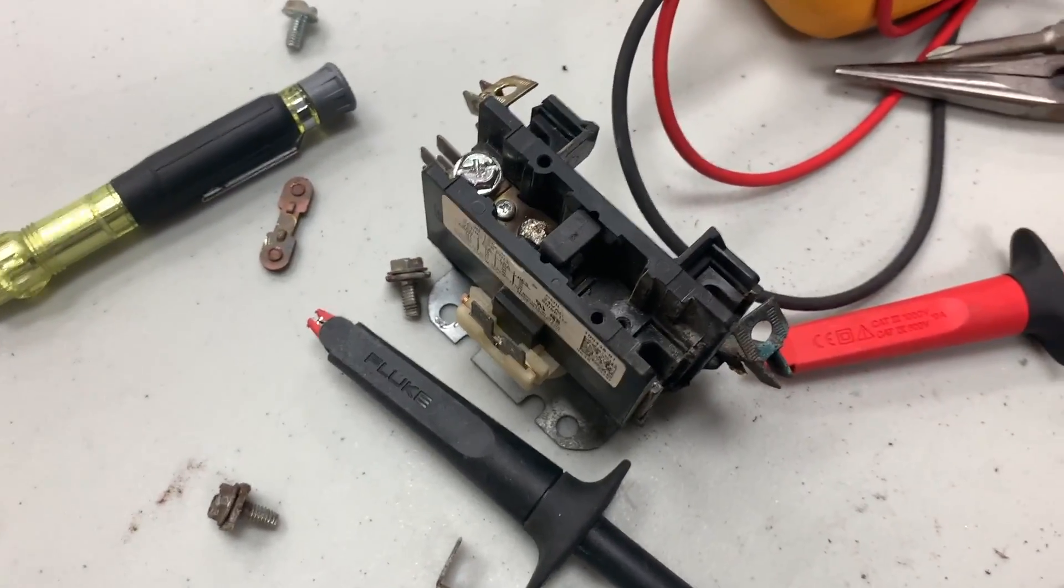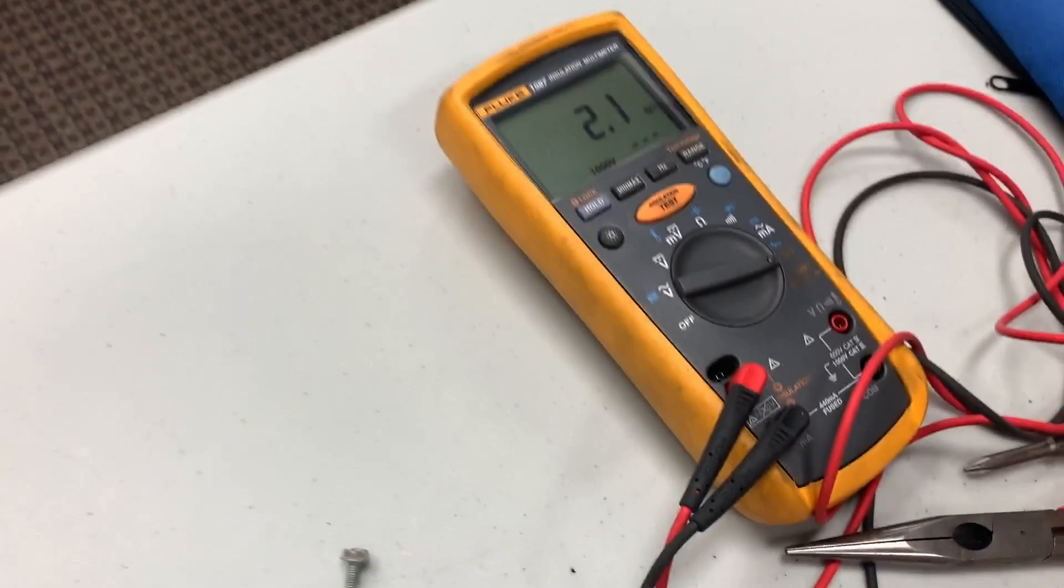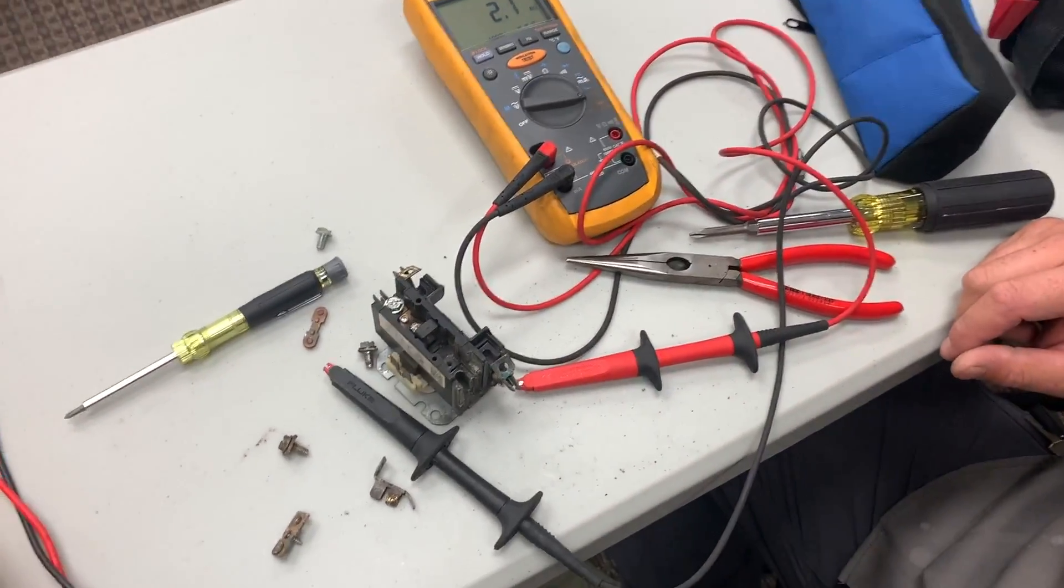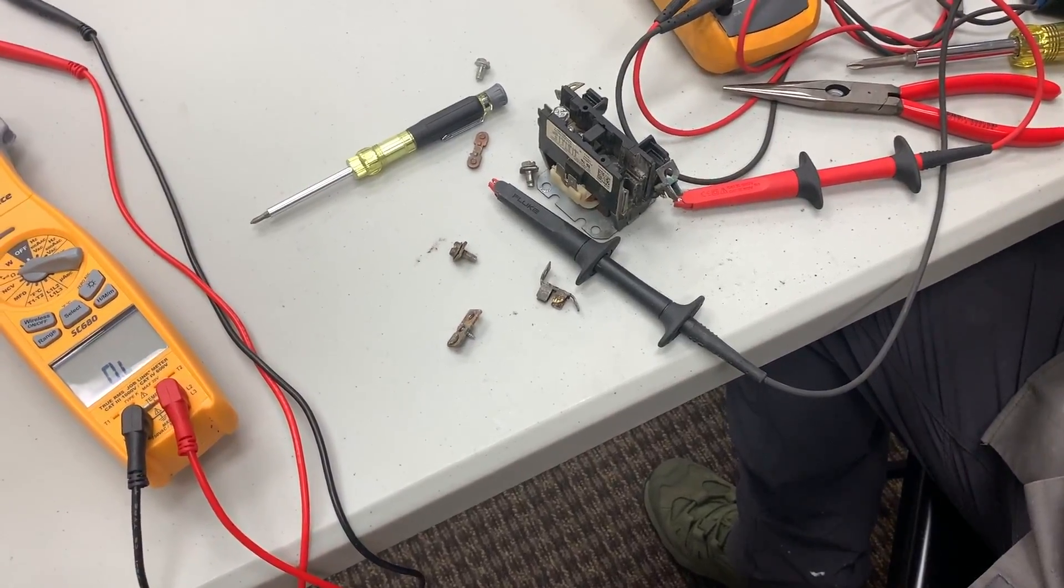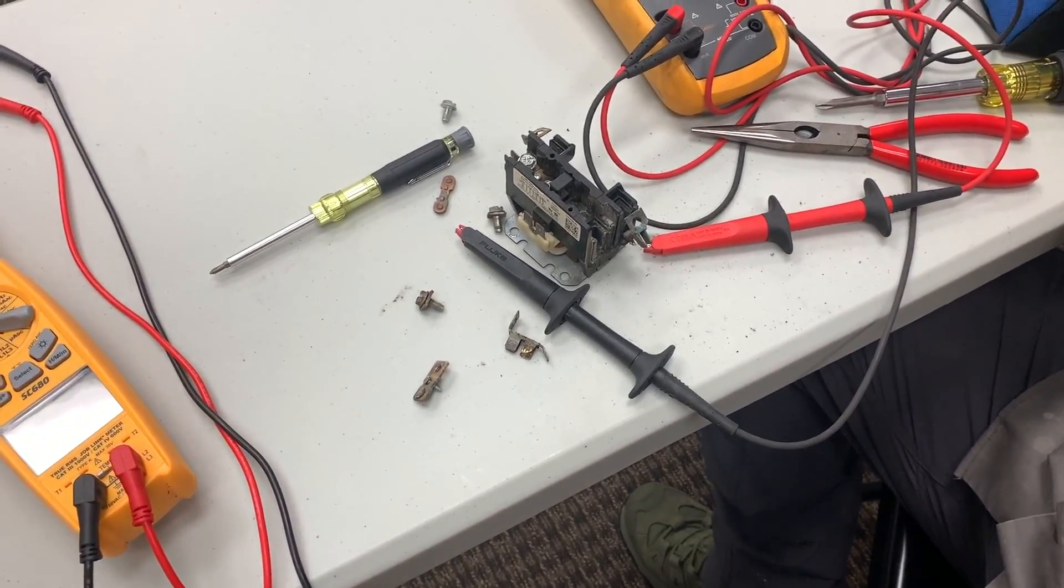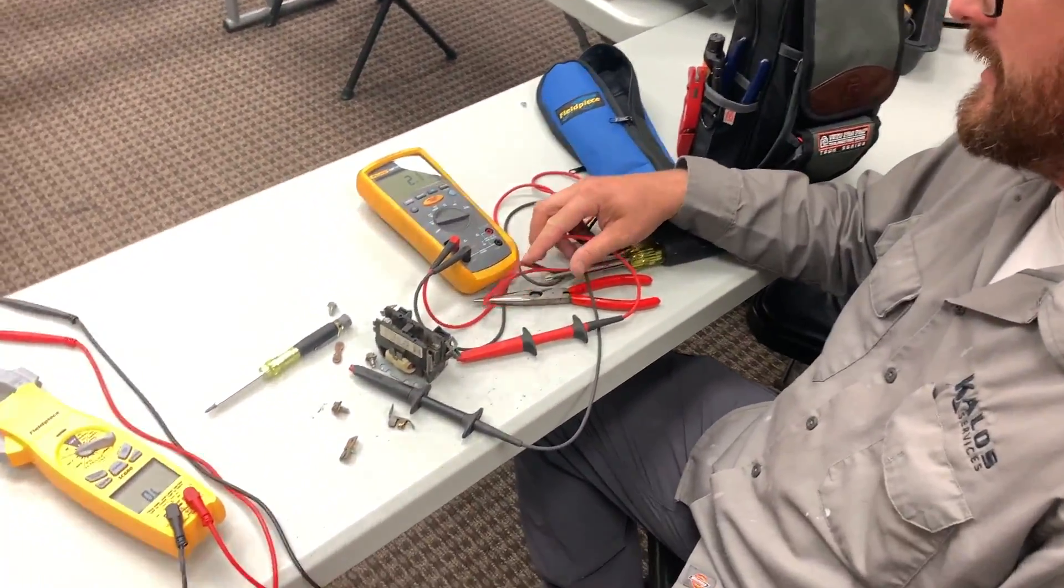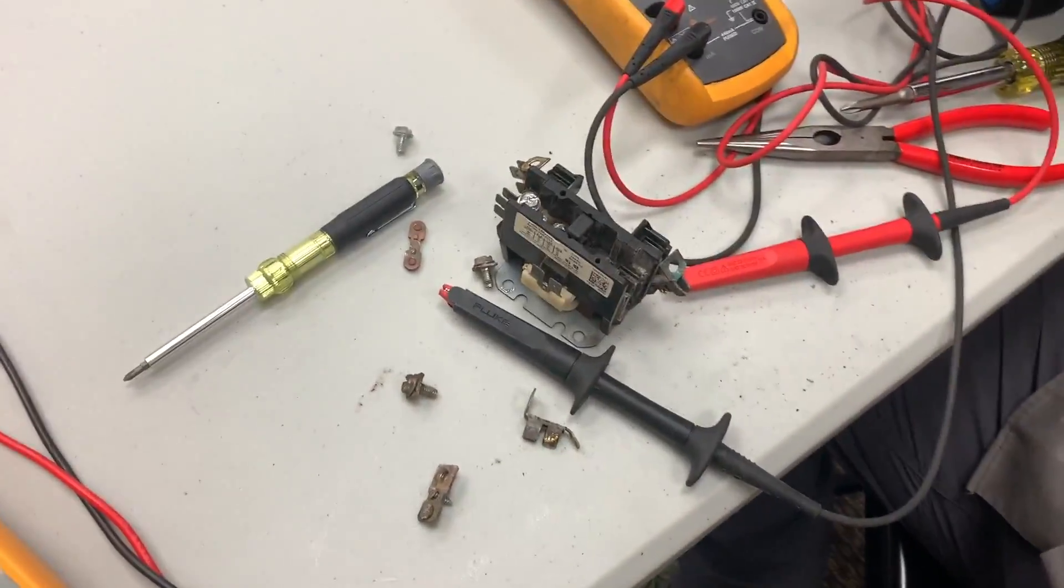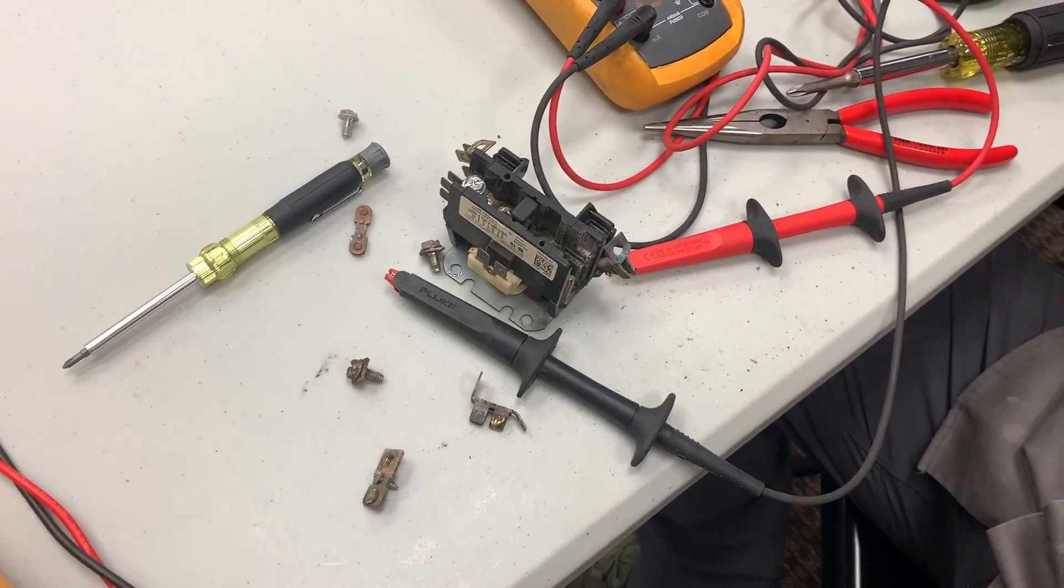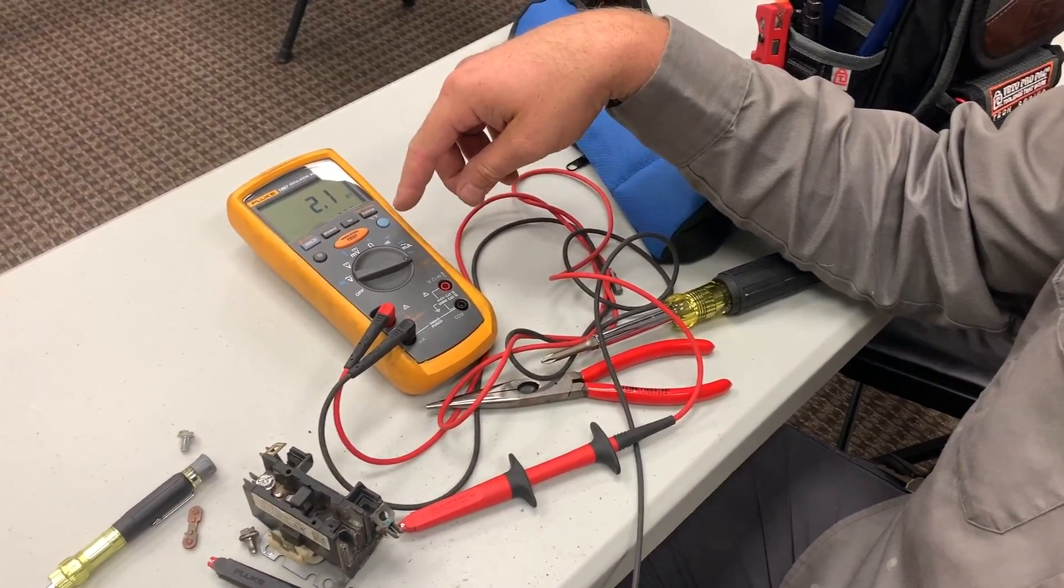What I learned here is that there are legitimately cases for megohmmeters and insulation testers in our industry. But in regular air conditioning, there's never been a case where I felt like I absolutely needed it to diagnose a problem. But in this case, I don't know. It's nice to have, and I have this one because it's not just a megohmmeter, it's a combination meter. I use the milliamps more than anything else on this meter.